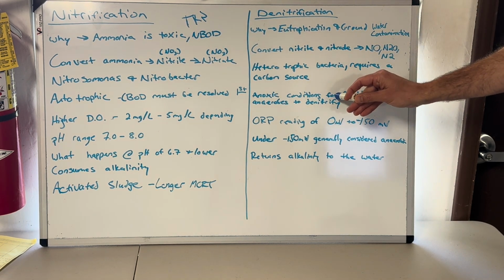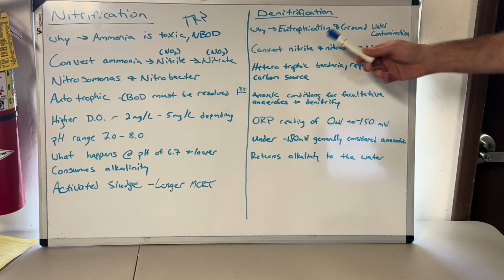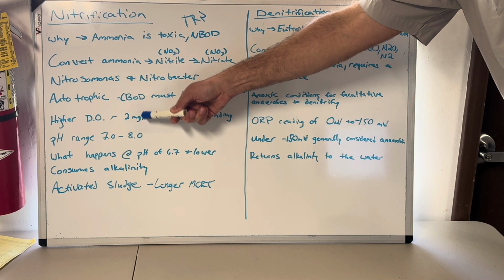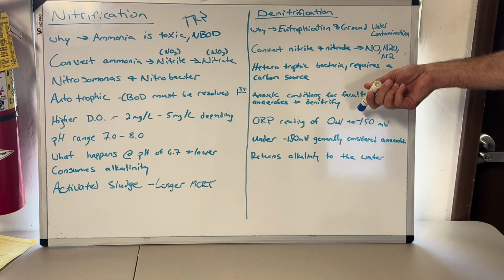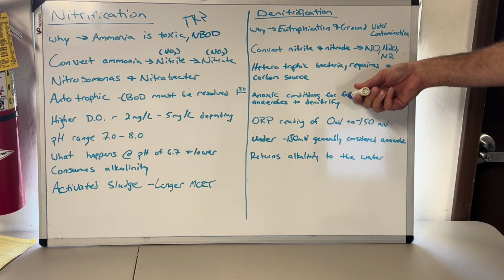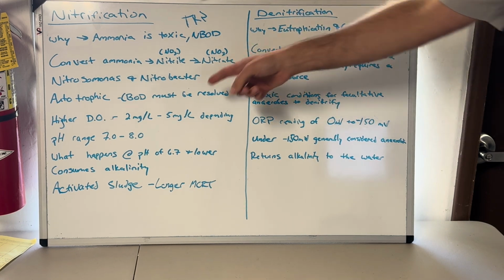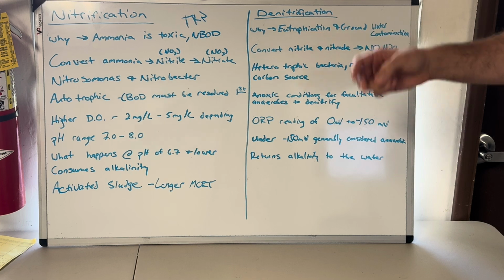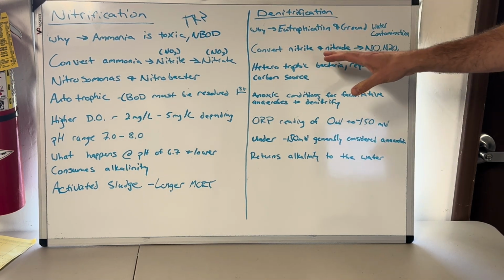Okay? And so you need to engineer this location to not have any dissolved oxygen present. No DO, but it's not anaerobic. Okay? Or else you won't denitrify. I mean, just by definition, if you've got nitrates in there and nitrite, it isn't anaerobic because there's bound oxygen present. So there's 3 places you can have in terms of what we're talking about. You have aerobic, dissolved and free oxygen is present. Anoxic, only bound oxygen is present. And anaerobic, no oxygen is present.